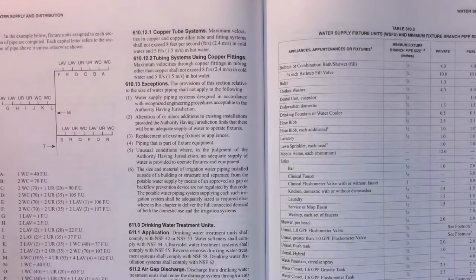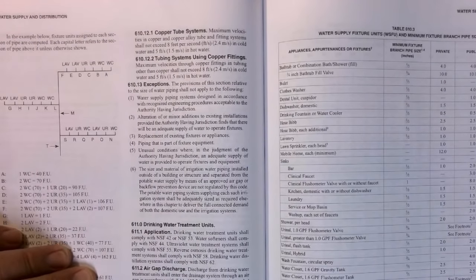And then I told you I'd talk a little bit about drinking water treatment units. Drinking water treatment units shall comply with the following standards. Water softeners shall comply with that standard. Ultraviolet water treatment system shall comply with the other standard, NSF 55. Reverse osmosis drinking water treatment system shall comply with NSF 58. Drinking water distillation system shall comply with NSF 62. So you have 42, 53, 44, 55, 58, and 62.